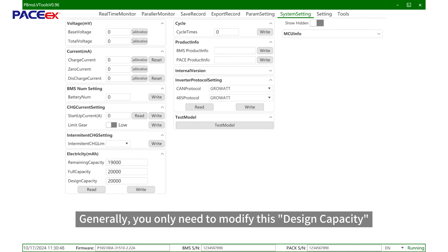There is the remaining capacity. Generally, you only need to modify this design capacity, because the remaining capacity and full charge capacity are learned through charge and discharge cycles. It should be set only when the battery cell capacity changes. For example, if a 200 Ah battery cell is used, but the written design capacity is 100 Ah, in this case, it cannot be learned.